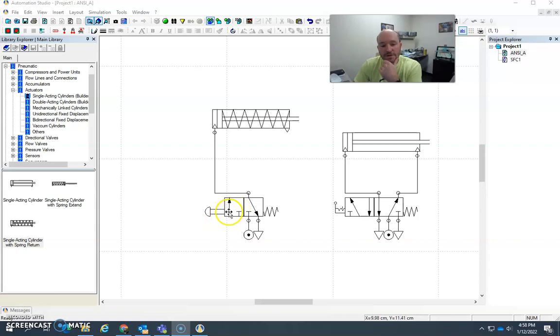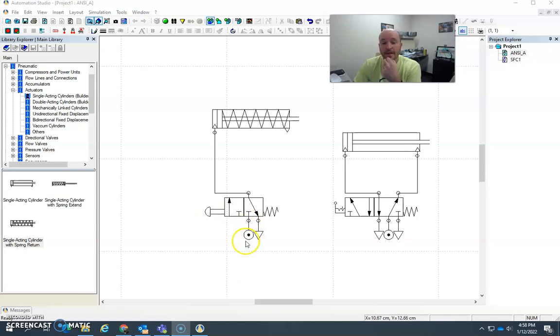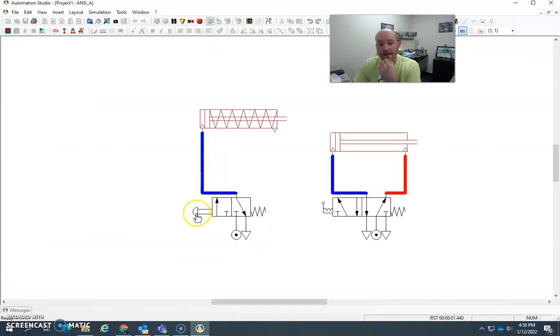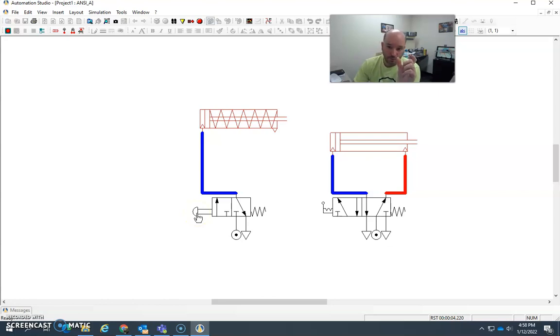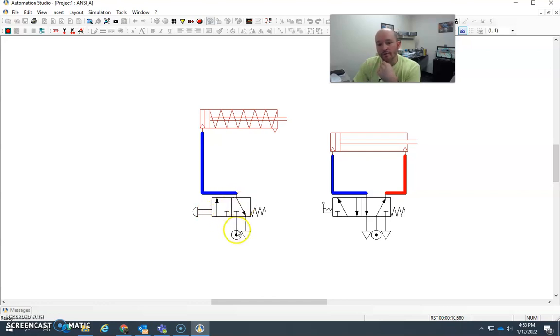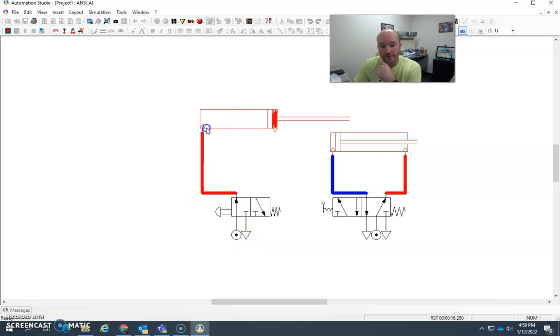So what I have here is a 3-2 directional control valve that is activated by a push button. And then we have a power source here and an exhaust. Now, when I activate this, when I turn it on and I push this button, the internal spool will shift. Schematically, what happens is this position here will move over to where the exhaust and the pressure port are. So I come here and I activate this. Air flows up and extends the cylinder.